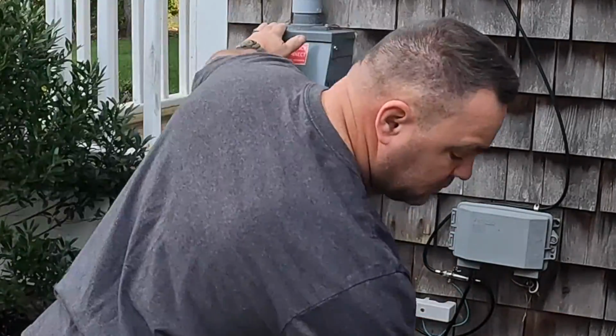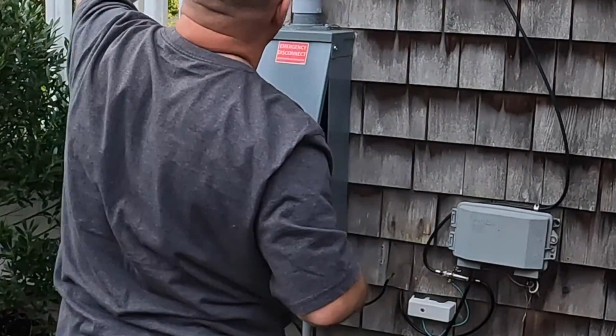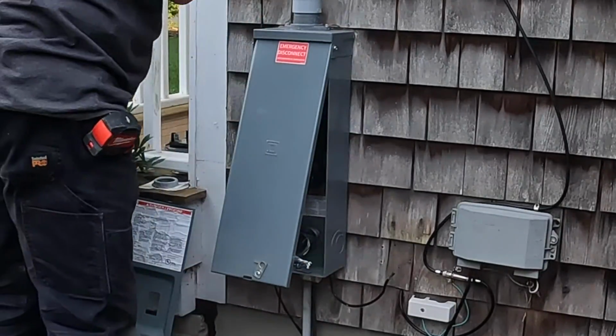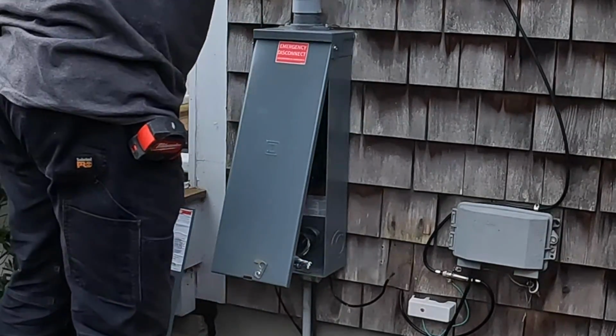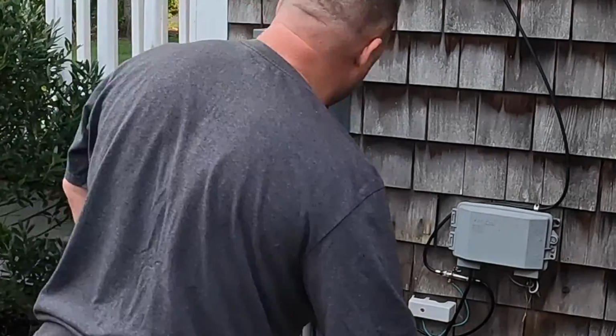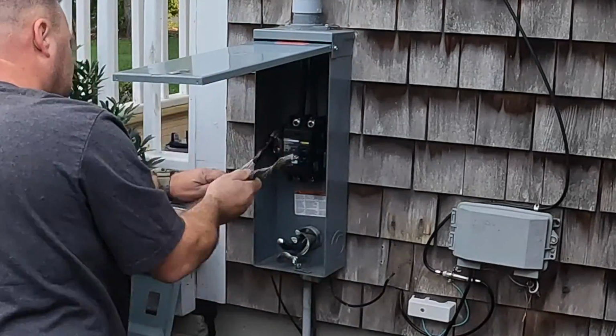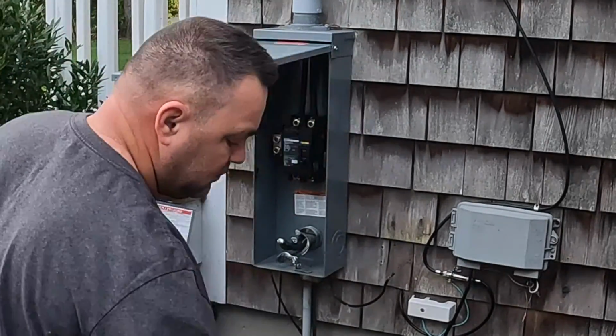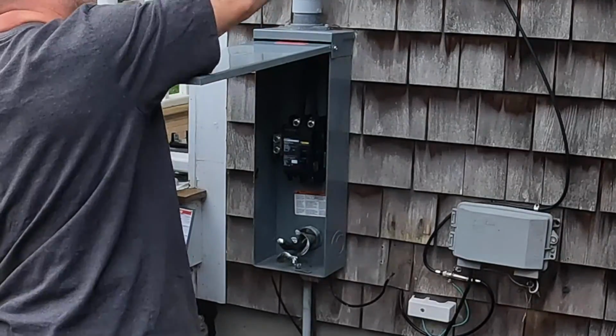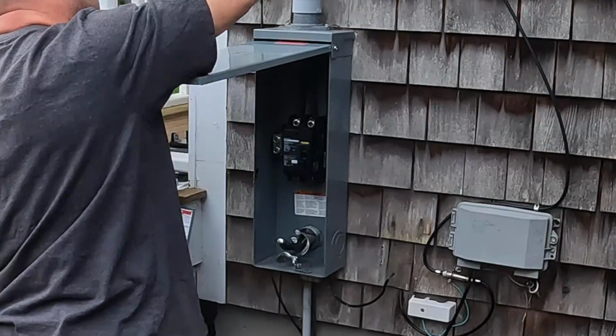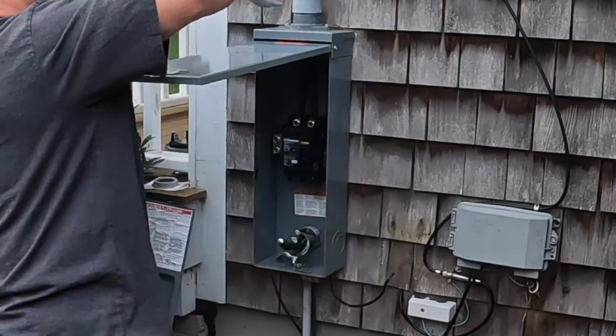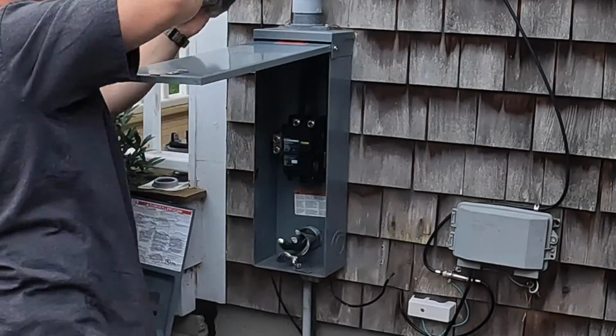So this is different than a service disconnect. This emergency disconnect does not contain any of the grounding and bonding required for a whole house service upgrade, which is at the main disconnect. This is separate from the main disconnect. This is just an emergency disconnect as defined by the National Electric Code. So what did I do? I had to go back up there and install this disconnect.